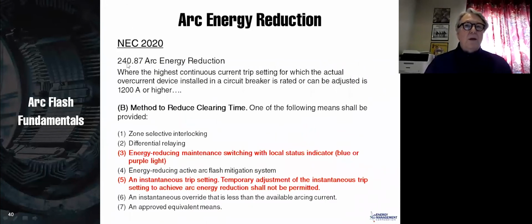Here's NEC 2020, paragraph 240.87, arc energy reduction, where the highest continuous current trip setting for which the actual overcurrent device installed in a circuit breaker is rated or can be adjusted is 1,200 amps or higher. You must have a method of arc energy reduction. So we're talking about circuit breakers, and they're saying if you can adjust that breaker to 1,200 amps or higher, then you must have some form of arc energy reduction. So what if you have a circuit breaker that has an adjustable trip that goes up to 1,200, but you only set it for 900?